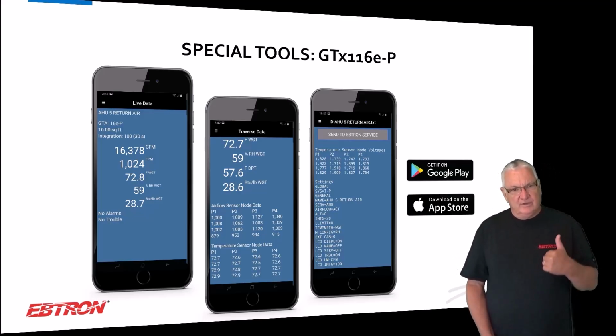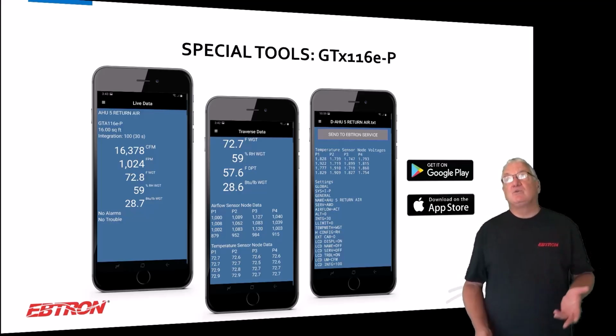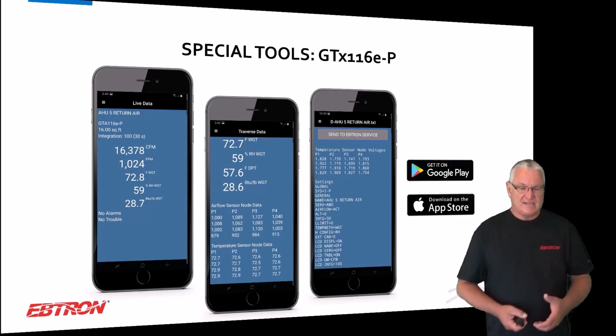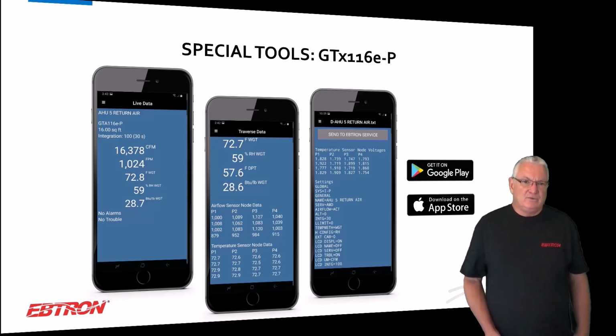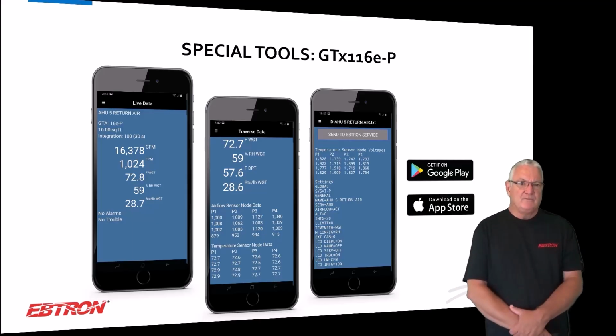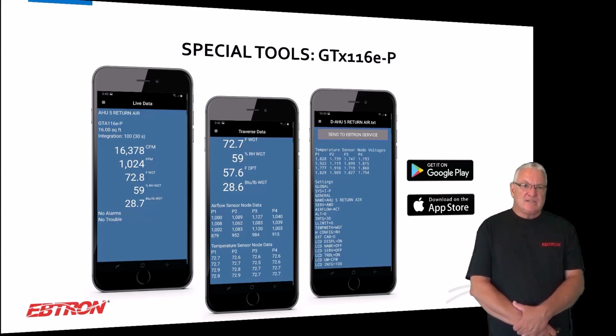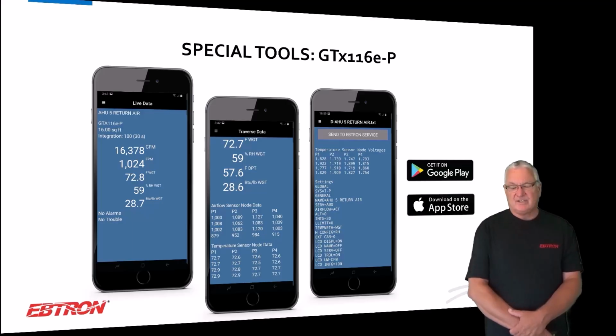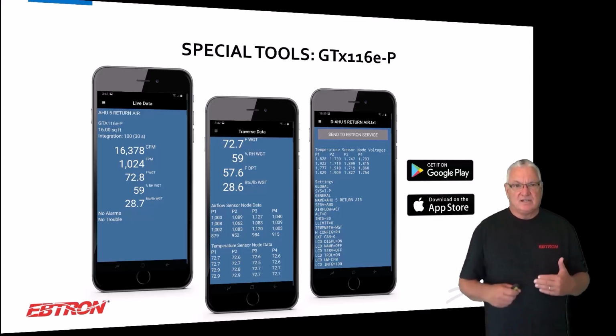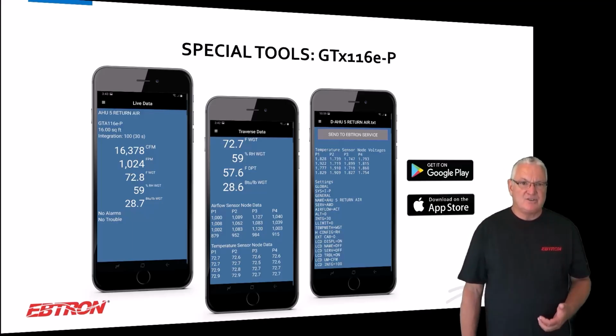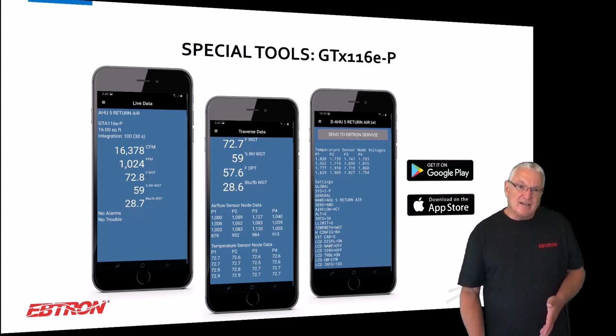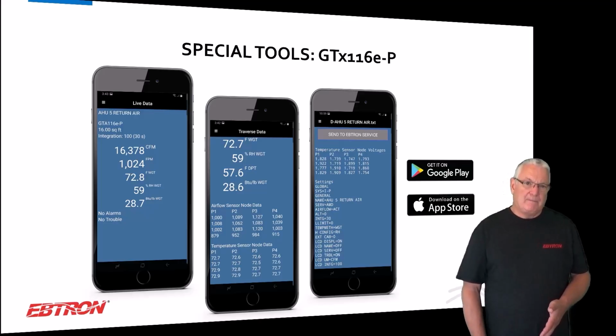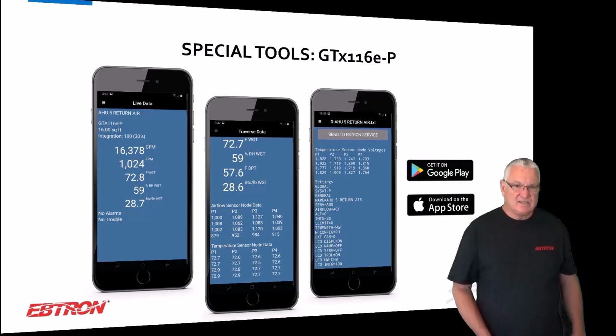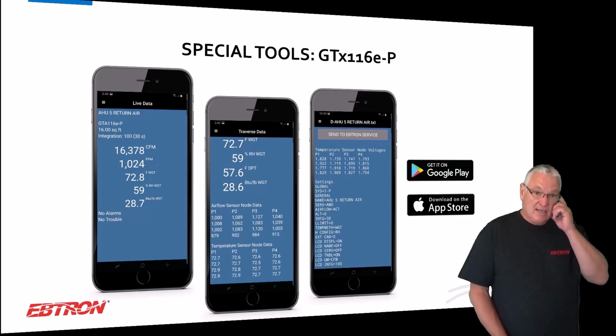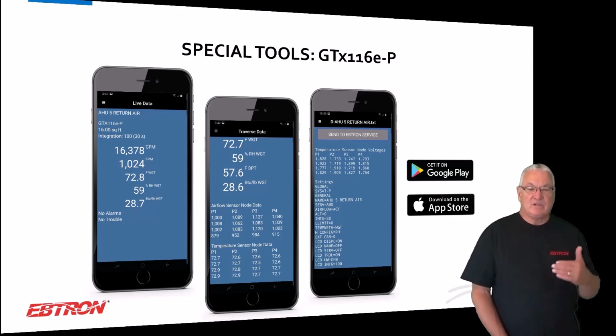So you'll get basically the first screen. You walk into a room, you get this app going, and the first thing that you see is what flow meters are in the room. We allow you to give us up to a 16-character name when you order it. I suggest you do that because it makes more sense to walk into a room and see something like AHU5 return air rather than the serial number of the unit. You can change it in the field, but to me it makes more sense to just name it in the first place.